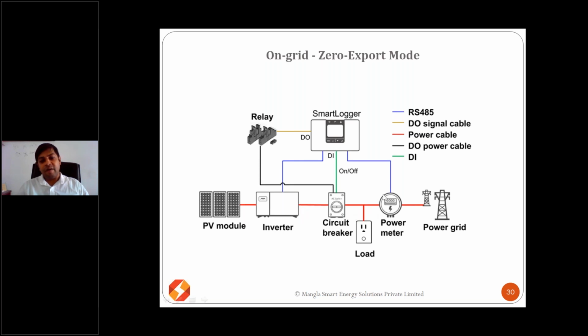This is when the grid doesn't allow you to feed in any power. For example, in Tamil Nadu, for the HT connections, rooftop solar is allowed, on-grid is allowed, but it should not feed any power to the grid in that condition. So it should be a zero export mode. For that system, you need to have a smart logger, relay, and a circuit breaker in addition to your existing components to make sure you use all the power you produce. Otherwise, you reduce your production in the inverter itself so that you do not supply any excess power to the power grid. So this is also very commonly used, mostly for HT connections.